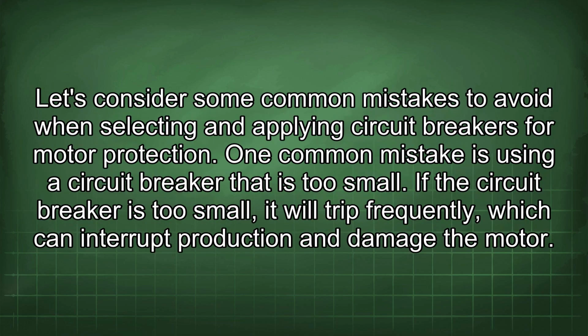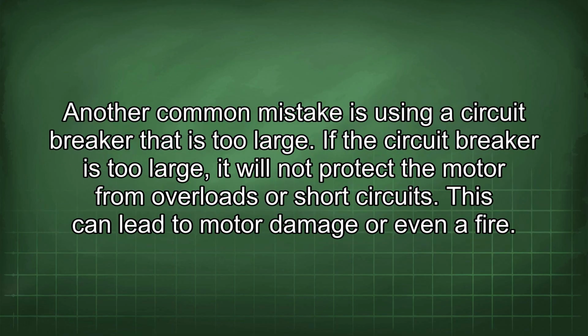Let's consider some common mistakes to avoid when selecting and applying circuit breakers for motor protection. One common mistake is using a circuit breaker that is too small. If the circuit breaker is too small, it will trip frequently, which can interrupt production and damage the motor. Another common mistake is using a circuit breaker that is too large. If the circuit breaker is too large, it will not protect the motor from overloads or short circuits. This can lead to motor damage or even a fire.